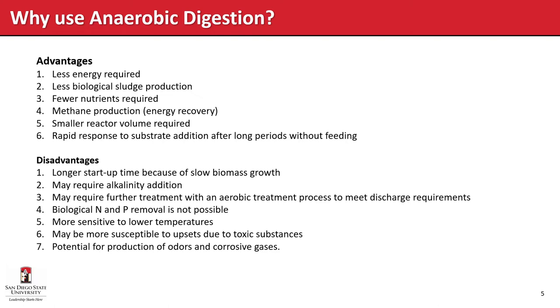Advantages of anaerobic digestion include very little energy required — we're really just putting in energy for mixing. We can produce methane and recover energy. Small reactor volumes are typically required because we want high-strength wastewater. Fewer nutrients are required, and there is less biological sludge production. The yield for anaerobic processes is much lower than for aerobic processes, which is one of the large benefits and the reason we can achieve solids reduction.